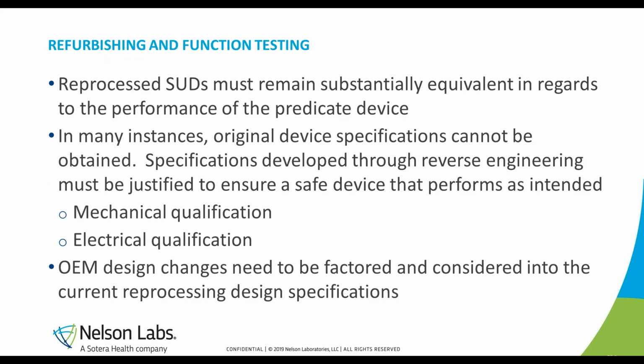Reprocessed single-use devices must remain substantially equivalent to the performance of the original device. As discussed, the original device specifications are typically not available from the third-party reprocessor, for the third-party reprocessor to develop design files and accurate functional testing. Therefore, specifications for physical, mechanical, and electrical attributes must be reverse engineered and developed through baseline testing. These newly developed specifications must be verified and justified to ensure the single-use device can be adequately reprocessed to a level that confirms the device performs as intended. Furthermore, original equipment manufacturer, original device manufacturer design changes need to be identified and accounted for in a timely manner to maintain the adequacy of reprocessing design specifications and associated function testing for the reprocessed device.